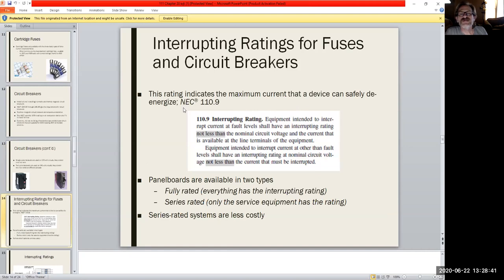So now if we go ahead and look up, yeah, I know this is so much fun, right? This rating indicates the maximum current the device can safely de-energize. And what do they mean by that? That means de-energized by the circuit breaker tripping or the fuse blowing, basically interrupting the power feeding that given line.